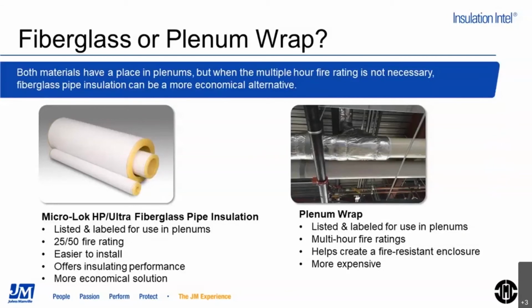Fiberglass. The 2550, when you do that, is, like Natalia says, totally different than plenum wrap. Plenum wrap will give you a one-hour or two-hour rating against the transference of fire through a mechanical system. That's why you have fire and smoke dampers in ductwork. That's why we do fire wrap on ductwork that is supplying an area that is subject to fire, so you can't transfer it. Piping is the same way. Anything that can transfer the flame spread from one room to the other, whether it's 1 hour or 2 hour, needs plenum wrap.